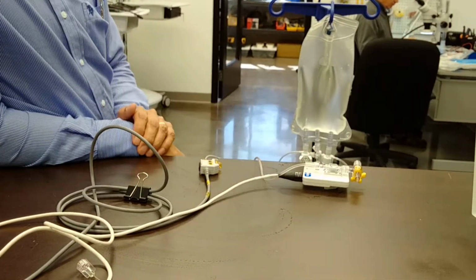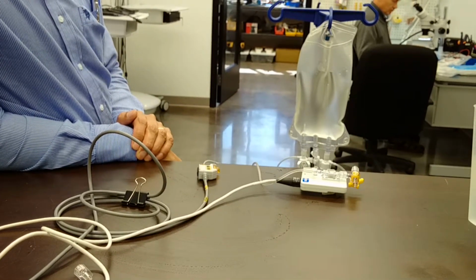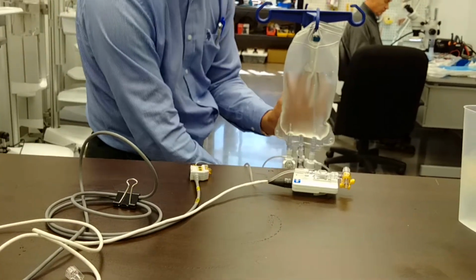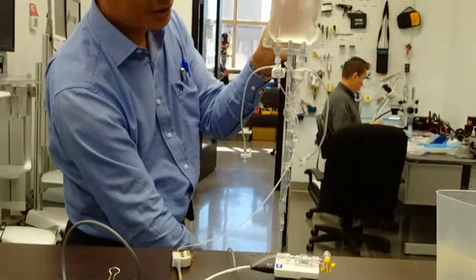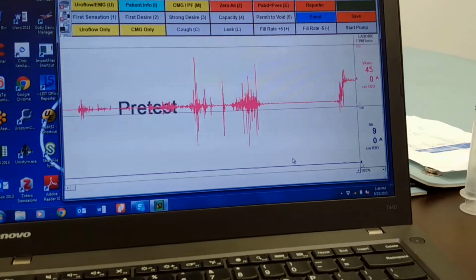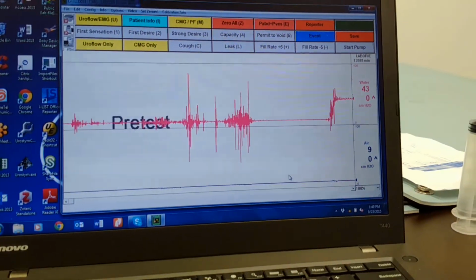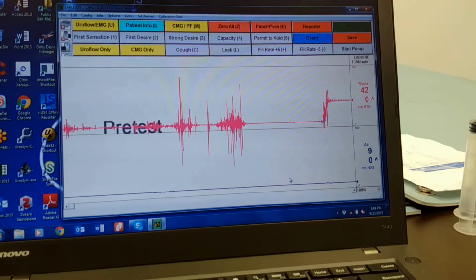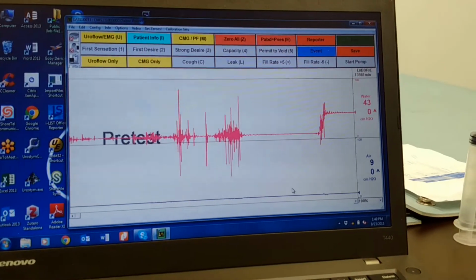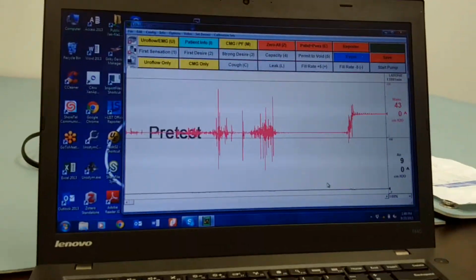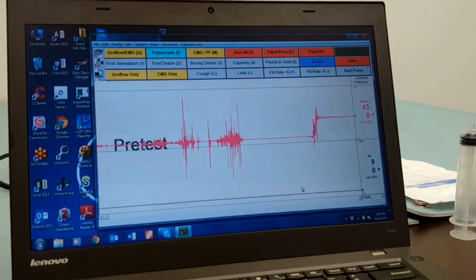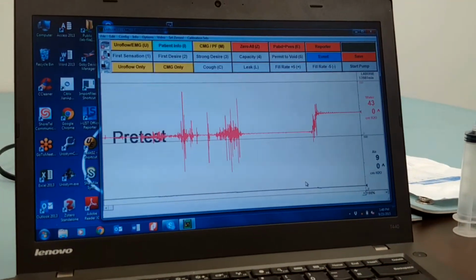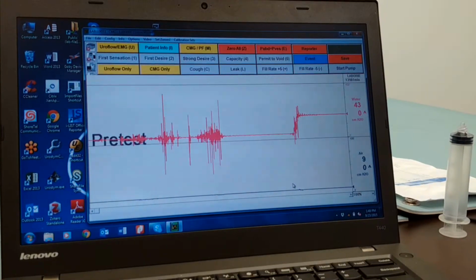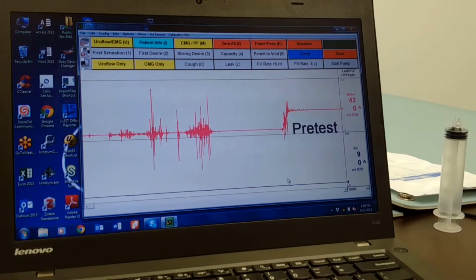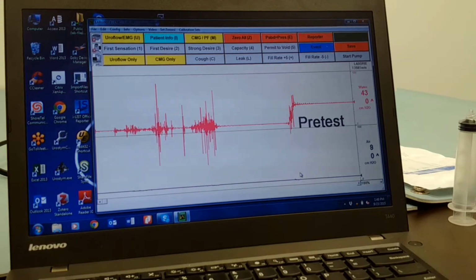If that transducer is not at the right reference level, then as soon as I raise it, say I raise it up this much, take a look at what happens on the computer screen. Now it's at 43. Notice the air is still at 9. It never changed. So the position of the transducer outside the patient relative to the symphysis pubis, which is the ICS definition of where that transducer has to be, is critically important. If that's too high or too low, your readings will be too high or too low.